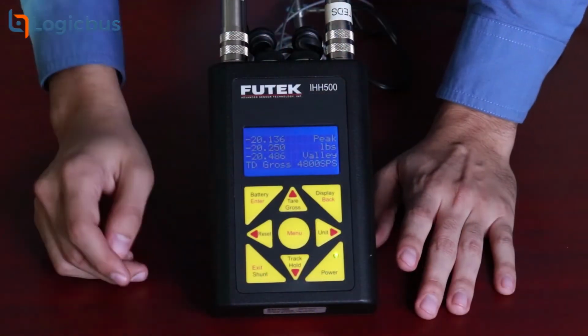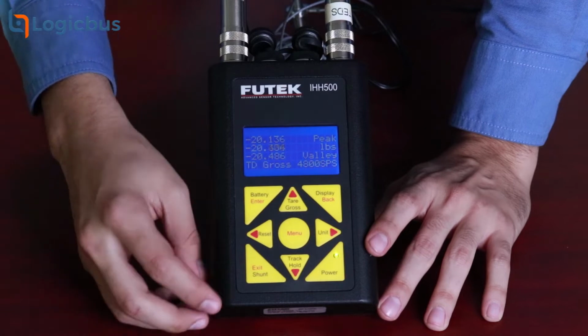Today, we are setting up our IHH500. This is a digital handheld display that we can use paired with a load cell. Remember that for this process, we're going to need our calibration certificate. So, let's get started.